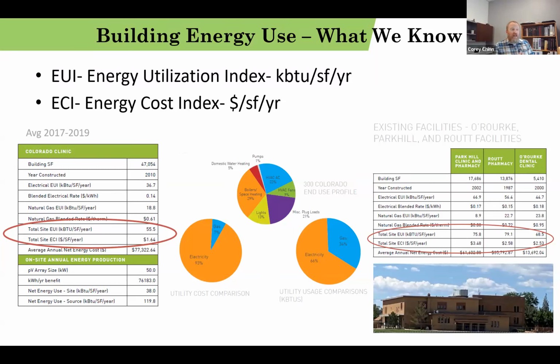So an average medical office building, according to Energy Star, is operating at about 107 kBTU per square foot per year. So our initial goal of 50% energy reduction, if we set that against Energy Star, we would see they already hit it in 2012. That's not an aggressive enough goal. That building is natural gas boilers, large air handlers, and hydronic reheat through VAV boxes. So we have to step up our game because this customer already does pretty good at using energy.